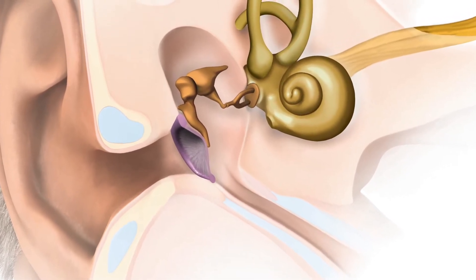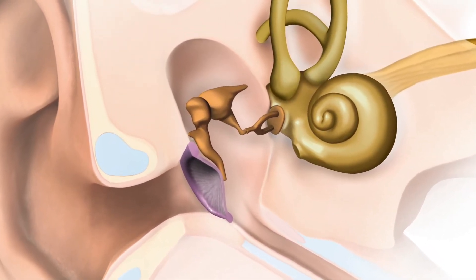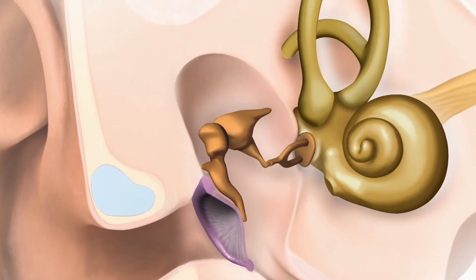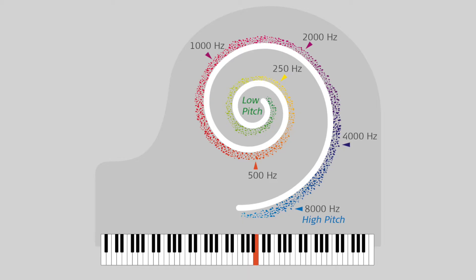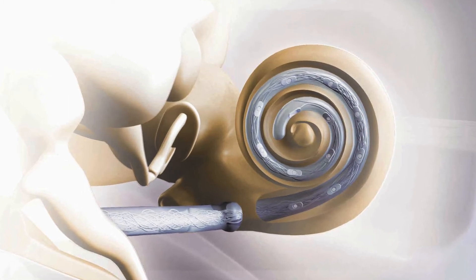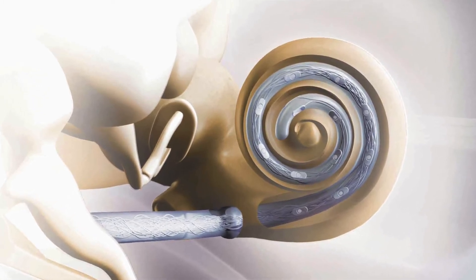The normal hearing ear expects frequencies to be presented at specific locations within the inner ear. A cochlear implant is designed to mimic this property, but can place these frequencies at the wrong locations. The length and position of an electrode array determines where these frequencies go.